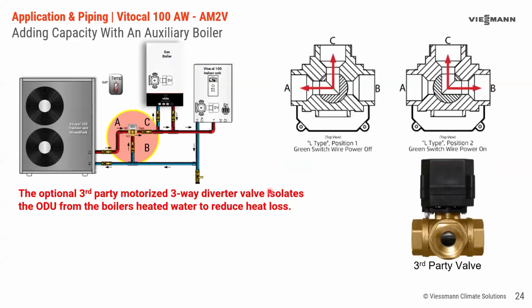Now, looking at this drawing here, again, we put the boiler here. In some cases, you might want to put this automatic bypass valve on it. And the reason why we say it's optional, you don't have to do this. Okay. But think about if I'm generating heat from this boiler and I'm going to be sending it to the system, some of it's going back to the outdoor unit and back to here. So my outdoor unit is going to be eating up heat just by ambient temperatures, right? Just by the heat loss through the ambient temperature. The heat pump's not providing anything for us at this point.